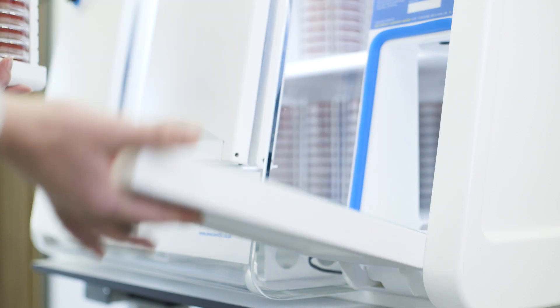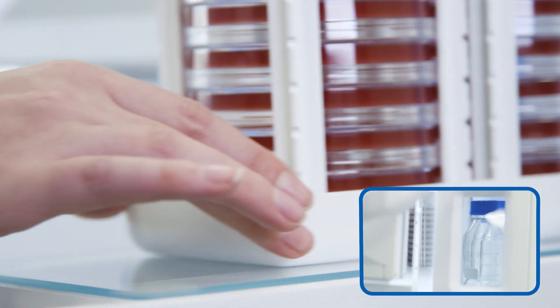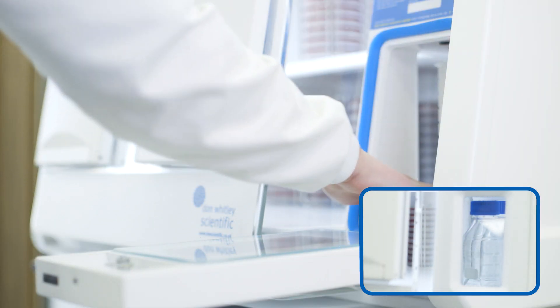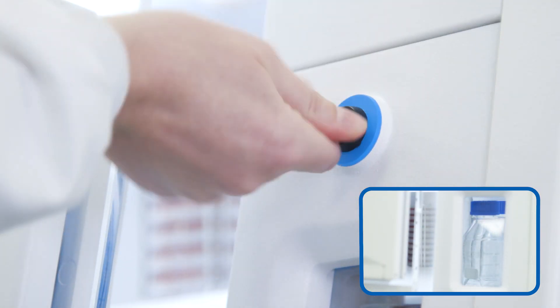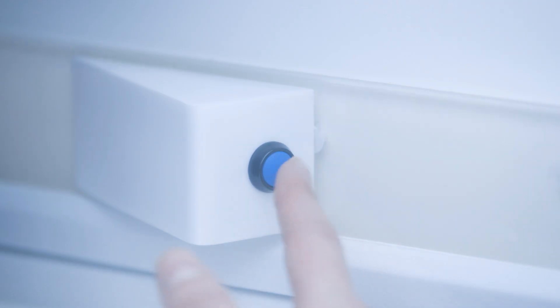The built-in rapid airlock, which can accommodate 20 Petri dishes or three 500ml Duran bottles, allows items to be transferred into the workstation atmosphere in less than 20 seconds. Doors are interlocked and cannot be opened simultaneously.